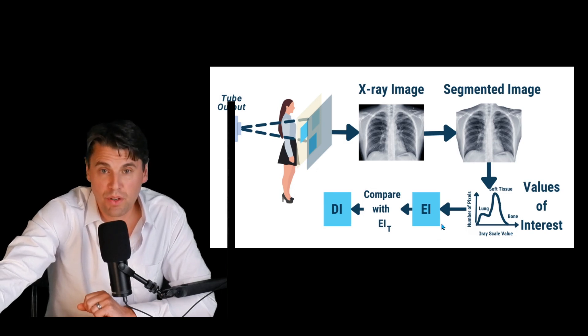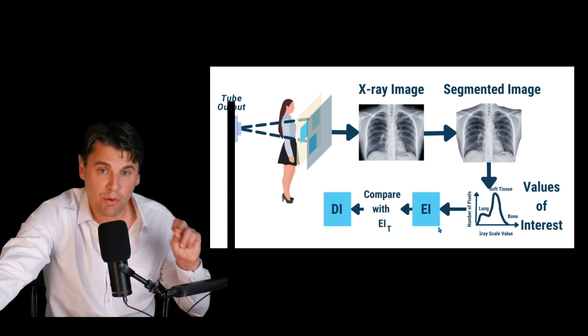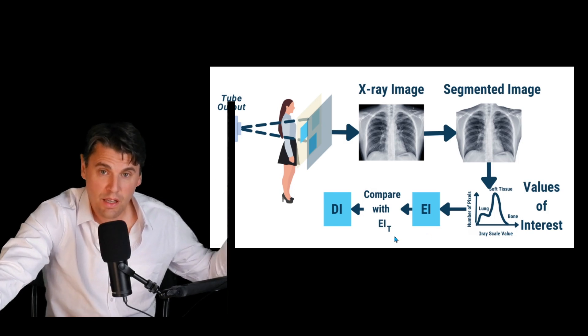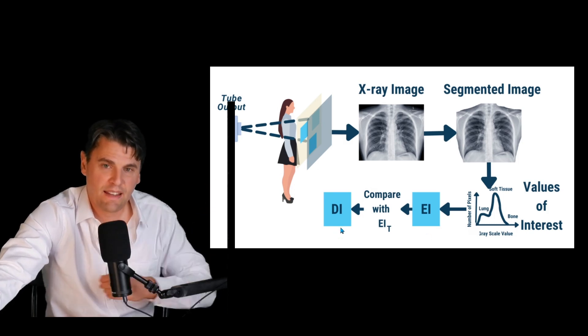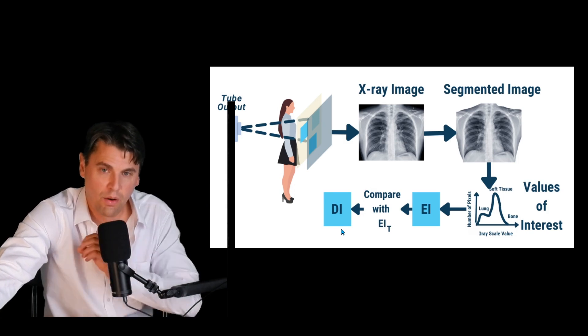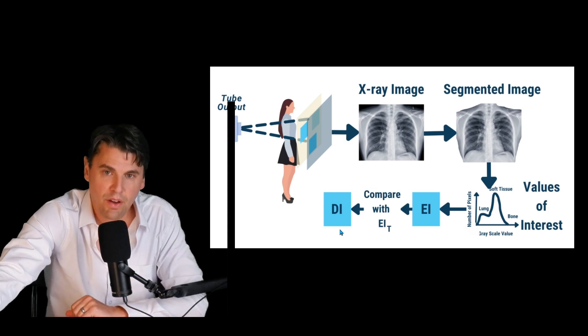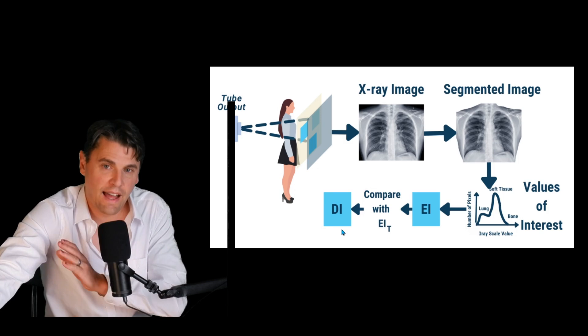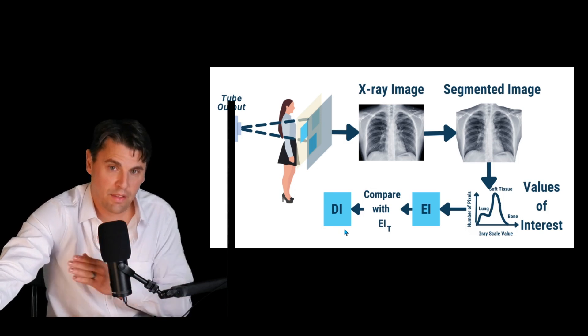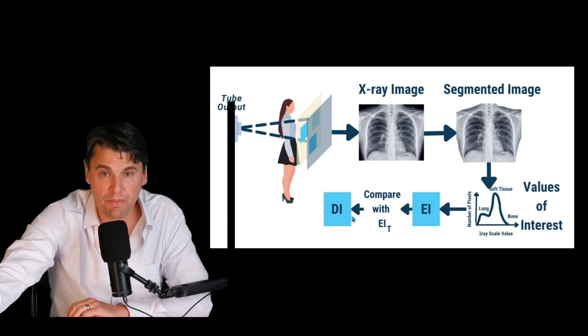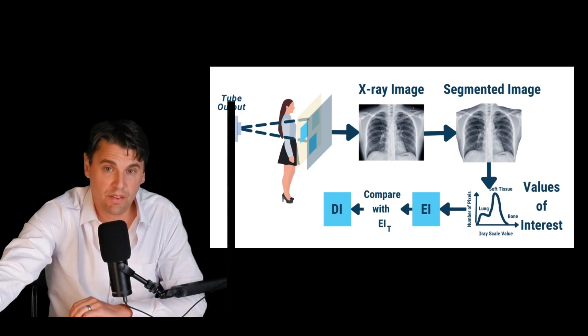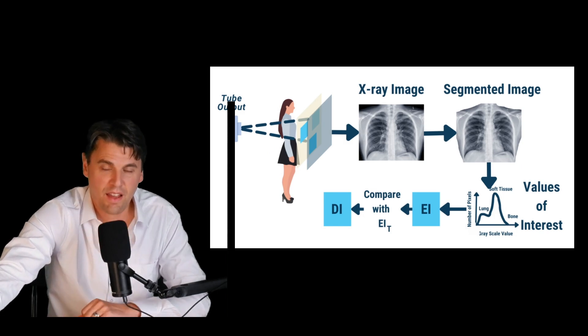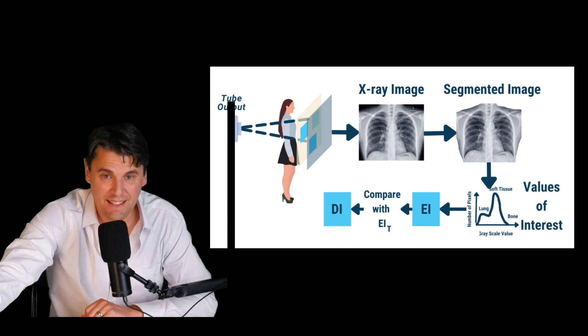Then from the exposure index, we can compare that exposure index with a targeted exposure, and we can get what we call a deviation index, or a relative deviation that we have from our target. But just at a high level, in replacing the built-in exposure monitoring on film, we now have a system of doing monitoring of the exposure index and talking about something called the deviation index.